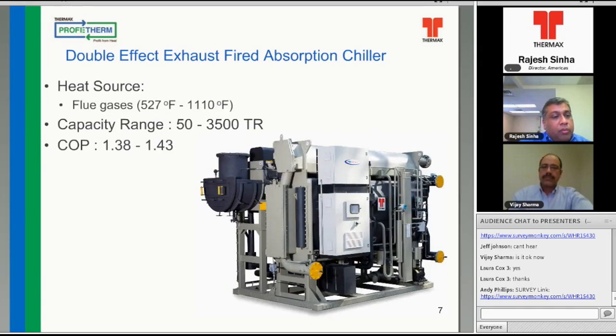The double effect exhaust gas driven absorbers can be deployed in conjunction with reciprocating engines, with microturbines or regular gas turbines, and these can handle flue gases even from recuperated turbines like the Capstones or Solar, between 527 to 1,110 degrees Fahrenheit. The capacity ranges between 50 to 3,500 tons, and the COP has a range of 1.38 to 1.43.